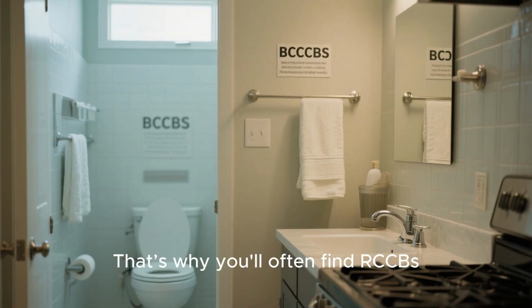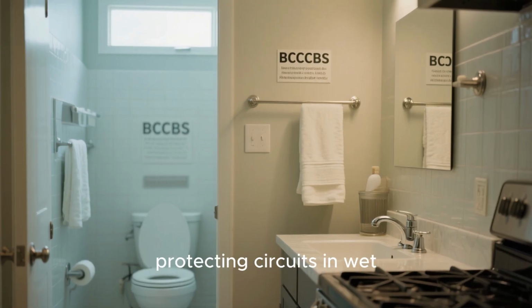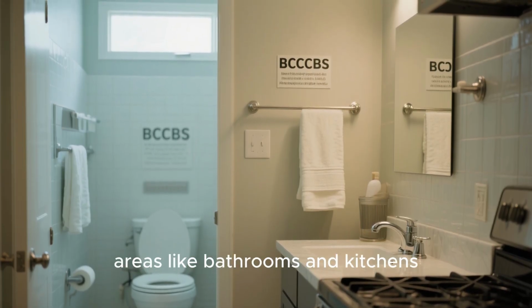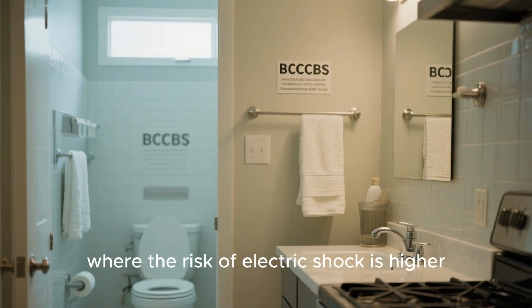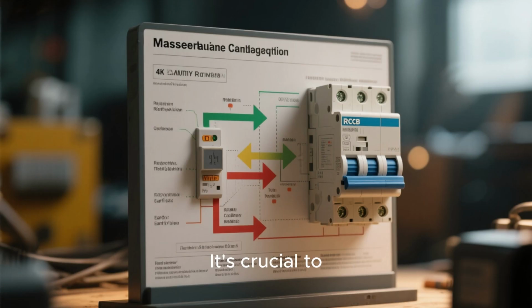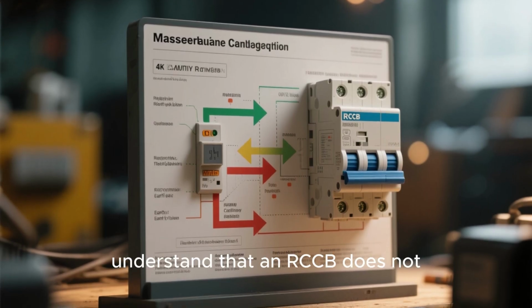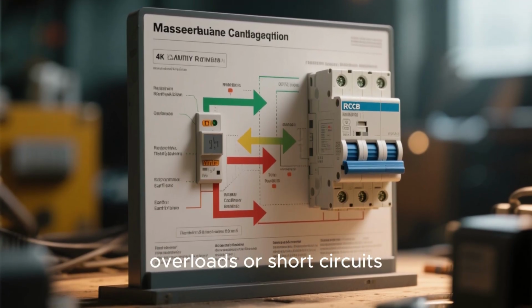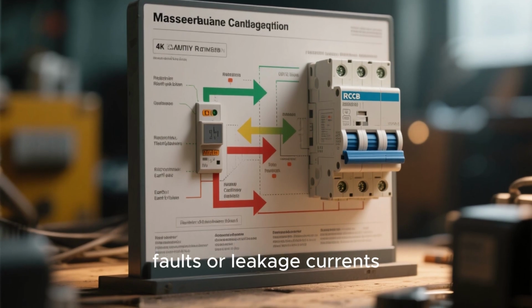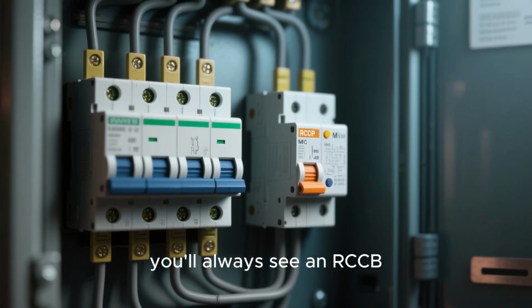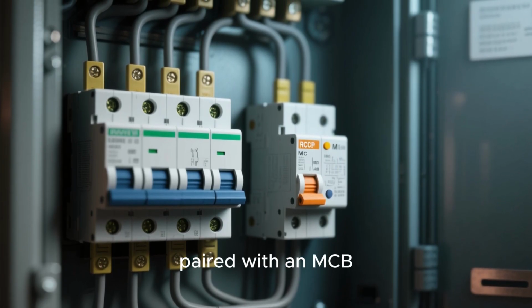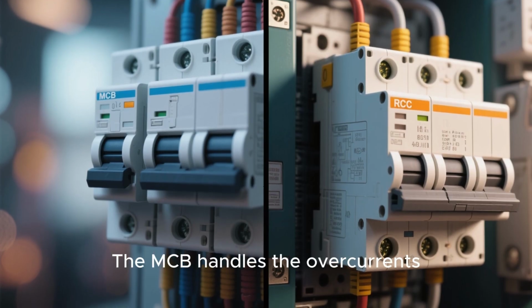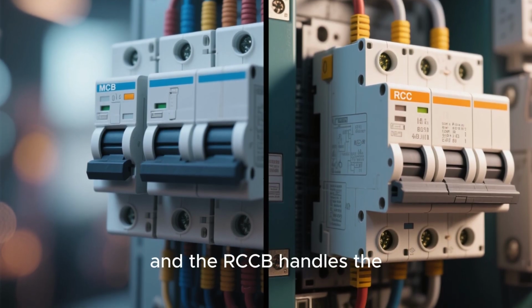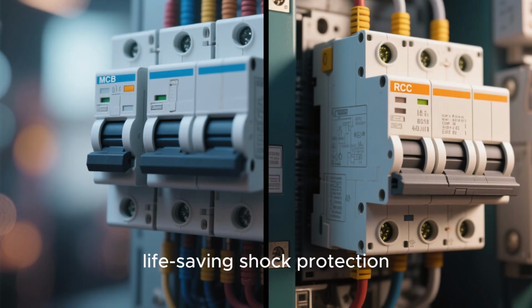That's why you'll often find RCCBs protecting circuits in wet areas like bathrooms and kitchens, where the risk of electric shock is higher. It's crucial to understand that an RCCB does not protect against overloads or short circuits. It only protects against earth faults or leakage currents. That's why you'll always see an RCCB paired with an MCB. The MCB handles the overcurrents, and the RCCB handles the life-saving shock protection.